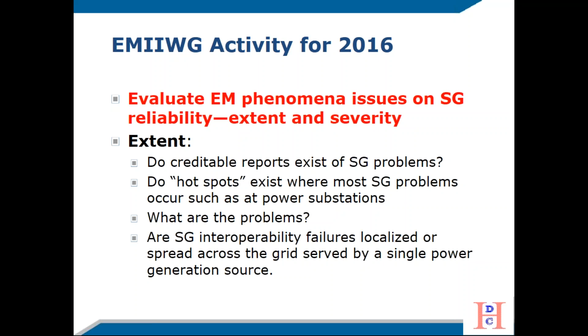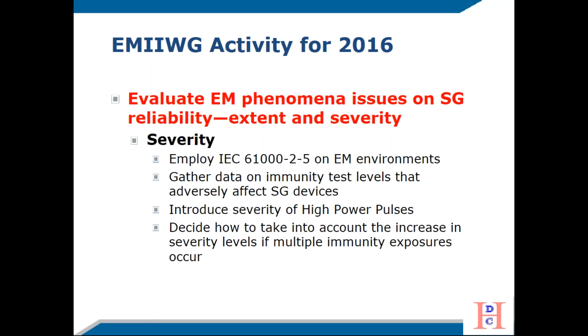Fortunately, we have an IEC standard that talks about the radiated field levels typical of EM environments, and it goes on for 20, 30 pages of tables at particular separation distances from the source. So even though they might give you typical electric field strength at, say, 10 meters away, if you're 2 meters away, the document doesn't necessarily give you guidance on how to insert that information into a near field equation and get a higher number. So we want to gather the data, and we know there's real concern with high power pulses, and how you take into account these multiple exposures I just mentioned.